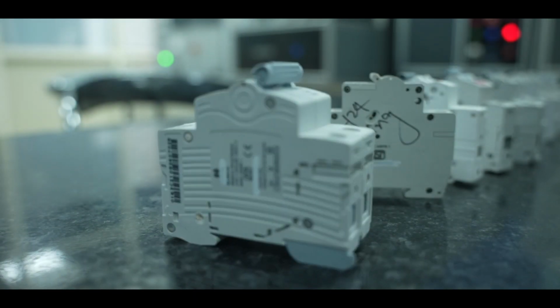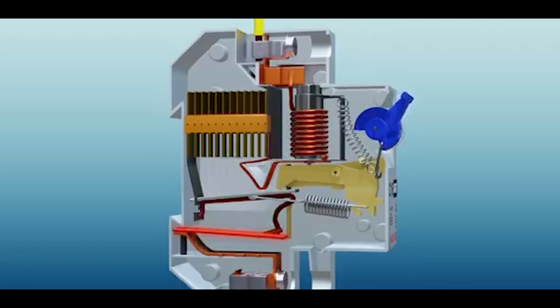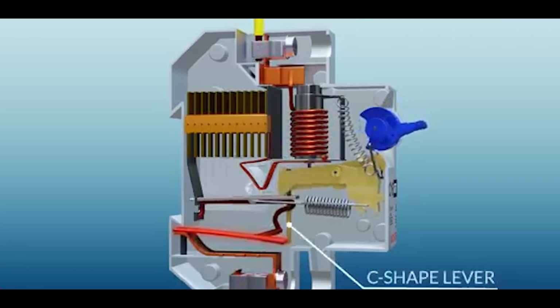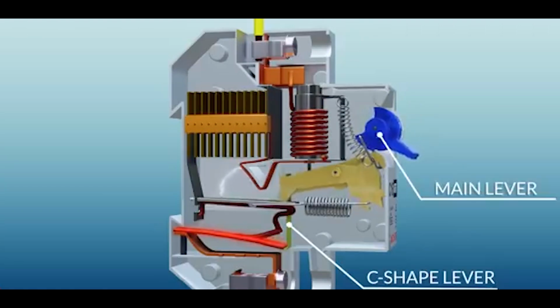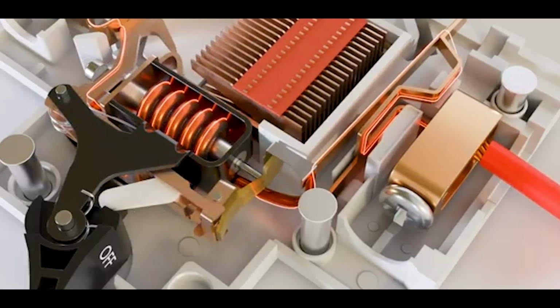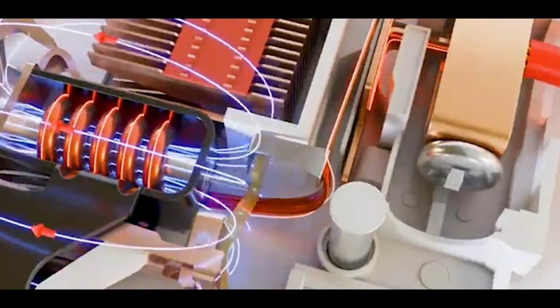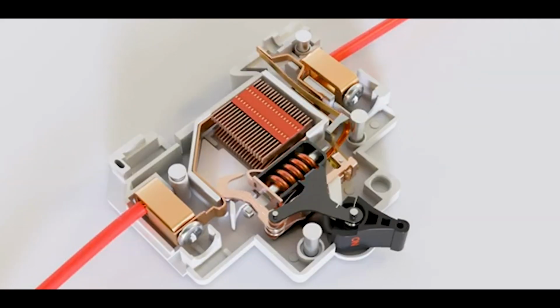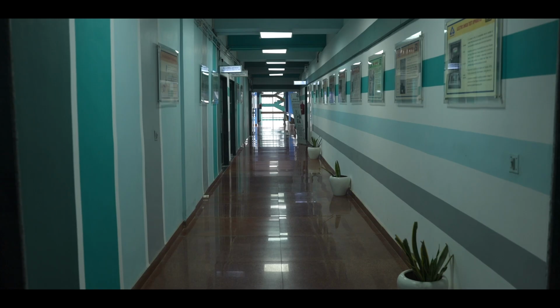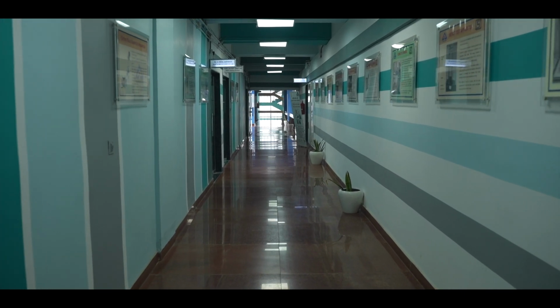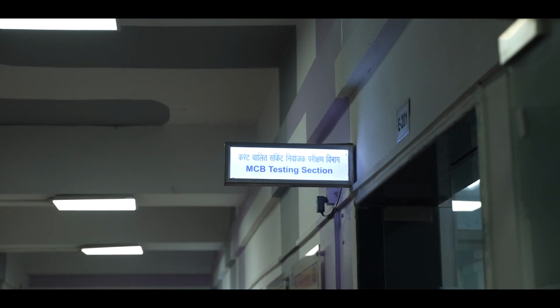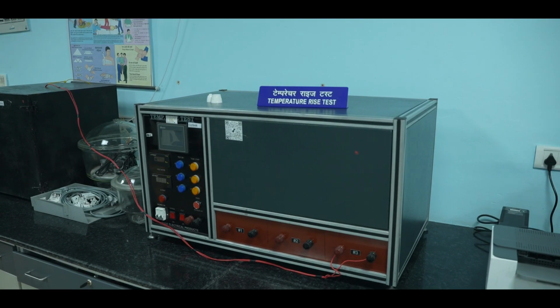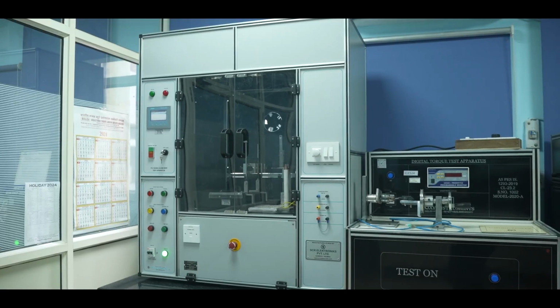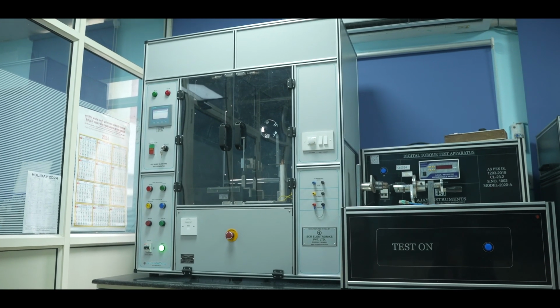An MCB is an electrical safety device designed to automatically shut off the flow of electricity when it detects overload or short circuit conditions. It protects electrical circuits and devices from damage and reduces the risk of fires or electrical hazards. In this video, we explore some of the essential tests conducted on MCBs at BIS laboratories as per IS 60898 Part 1. These tests ensure the safety, reliability, and performance of the devices.